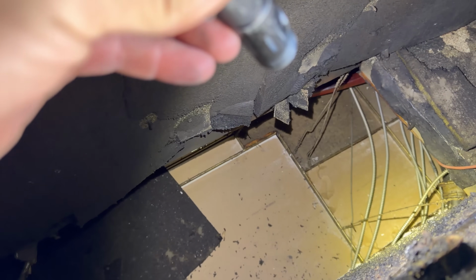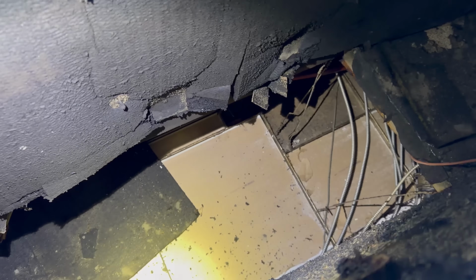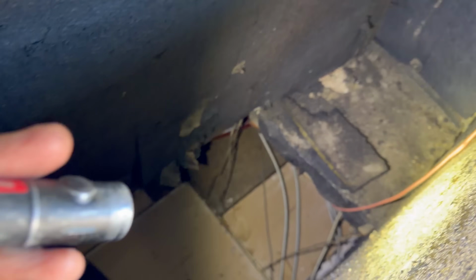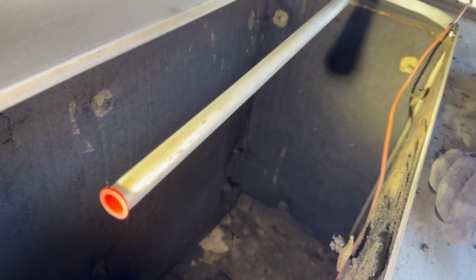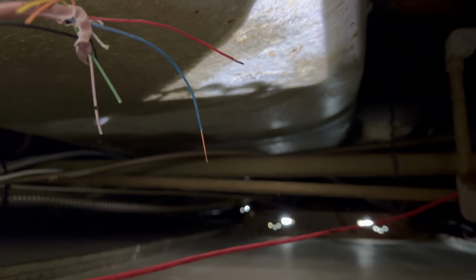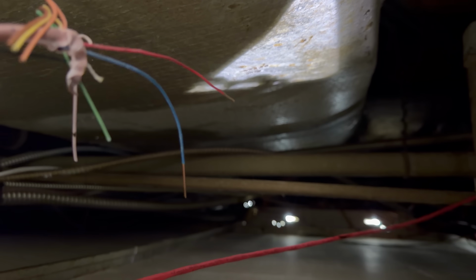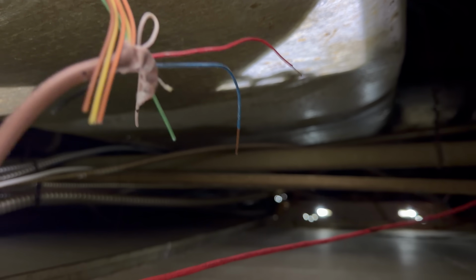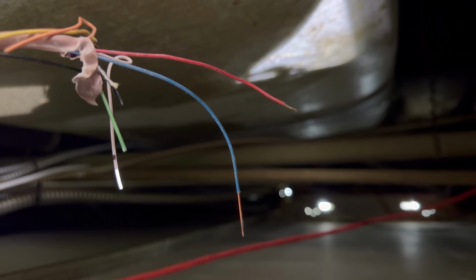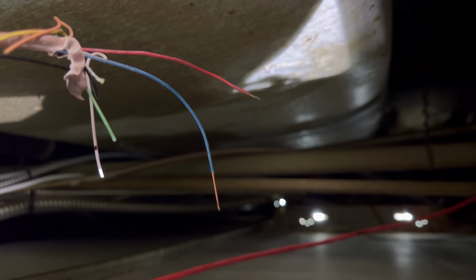So, yeah, this one, their attic fills up with grease. I forgot about this one. It's a mess. So that's the thermostat. So that's not the zone sensor. Let's see if we can find the zone sensor. It's somewhere else. Well, we found where the zone sensor should be. Someone took the zone sensor out and just left the wire sitting in the attic. So no wonder the thermostat's not reading temperature.